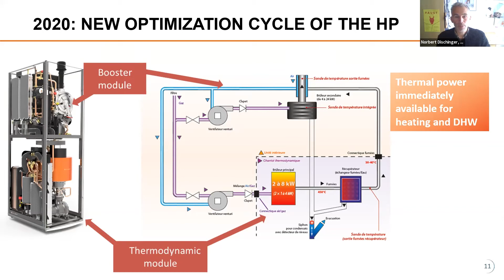And we need to connect to the chimney system, at least in the Germanic countries. In Southern Europe, sometimes it's easier. And we need to connect to the condensed water garbage system. Our efficiency values, which we have proven and shown in the field so far, yes, they depend on the heating circuit temperature. The characteristic of the machine is that the higher the split in the heating circuit in temperature, and sure, the lower the temperature, the higher the overall efficiency. But as we are driving the compression by burning gas with an open flame, we already have at hand the driving energy as a heat source. So half of the necessary heat is already available at hand, and the second half is brought in by the heat pump mechanism.